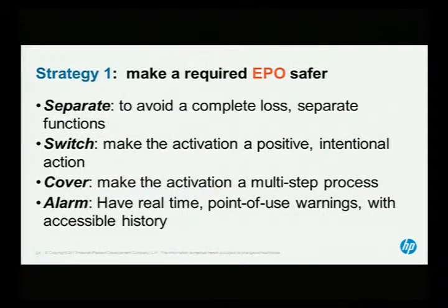Number one, if you're going to have an EPO, make it safer, okay? Separate the functions, use a switch. Make the activation a positive intentional action as opposed to a bump and run. Cover it and have an alarm. Now we'll give you some examples of this.